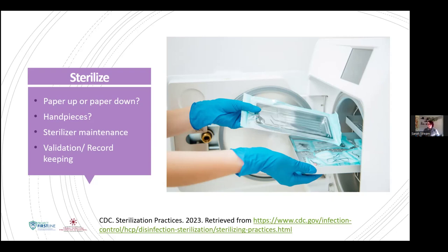Sterilization maintenance is an important part of a successful sterilization process. If your sterilizer is not being maintained, there's greater chance that it will fail. And there are maintenance procedures that staff can do internally, but there are also things that should be done by a technician that knows how to work on those sterilizers. And any maintenance that's done should be documented and recorded in case of an audit.